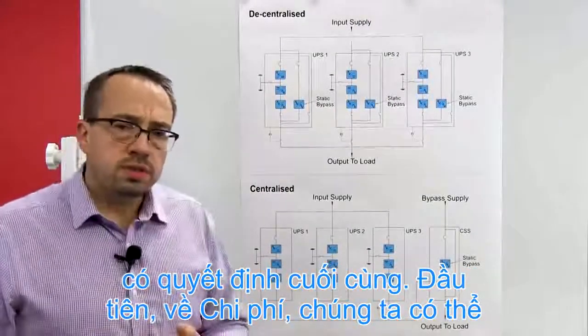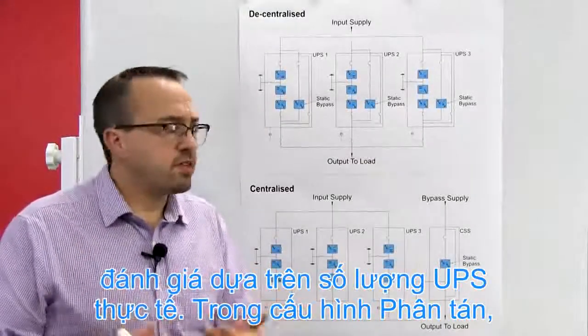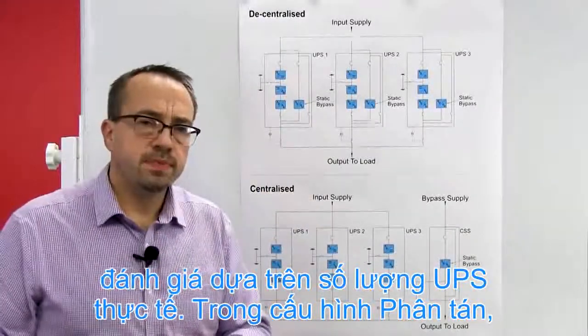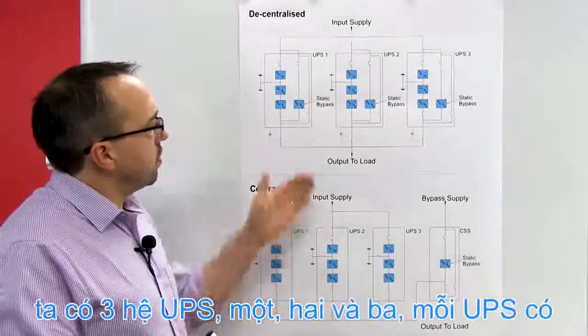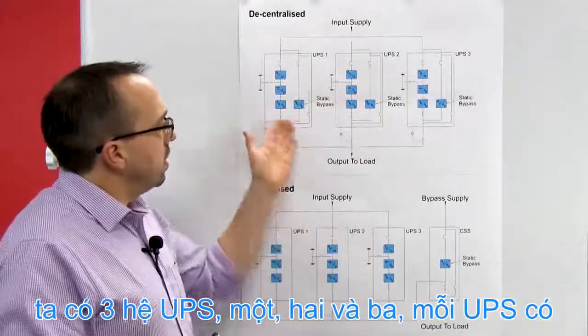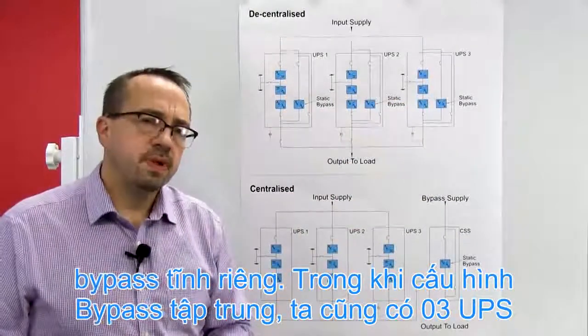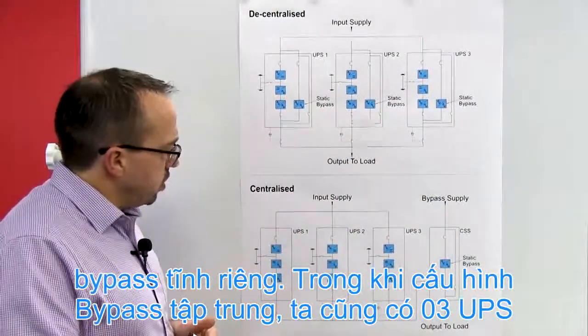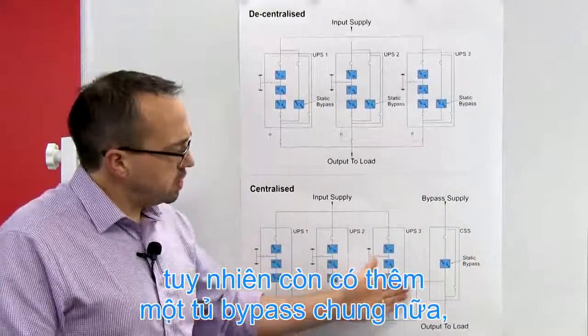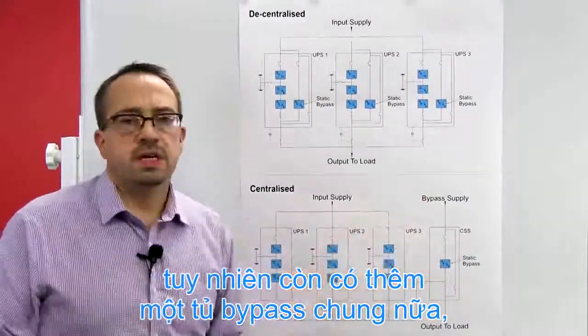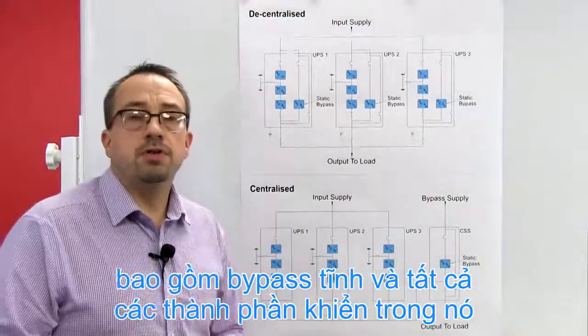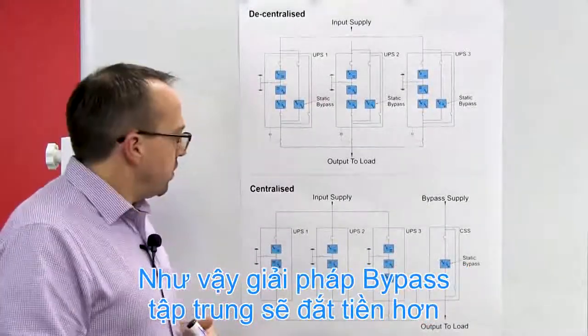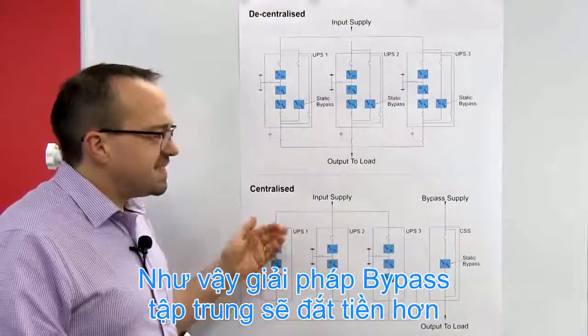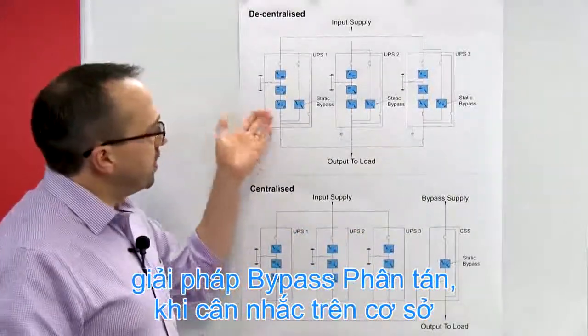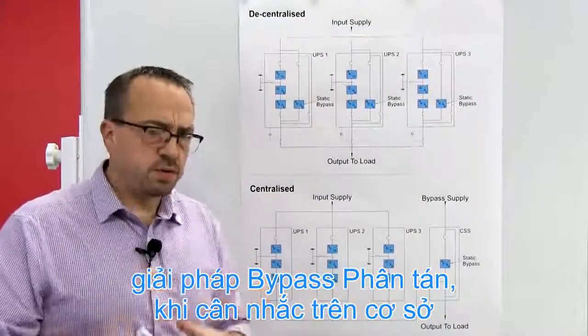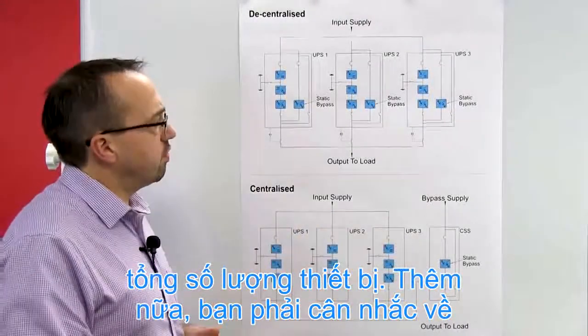Firstly, if we look at costs. In terms of costs, we can split this down firstly into the actual UPSs themselves. In the decentralized system, you've got three UPS systems, 1, 2 and 3, each with their own static bypasses. Whereas in the centralized system, you've again got the three UPS modules. However, because you've got the additional fourth cabinet, which contains the static bypass and all of the controlling architecture within that system, the centralized bypass solution is typically slightly more expensive than the decentralized approach, and therefore just something to consider in terms of the overall equipment.